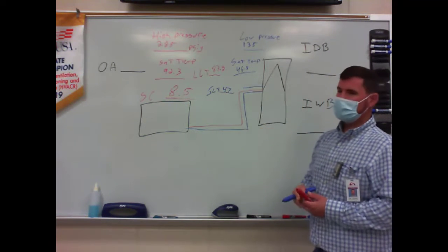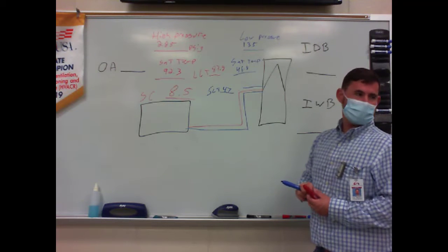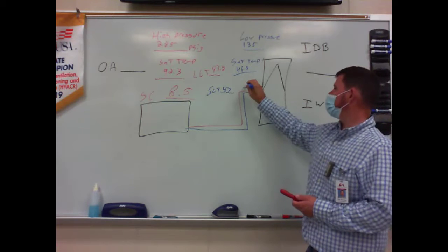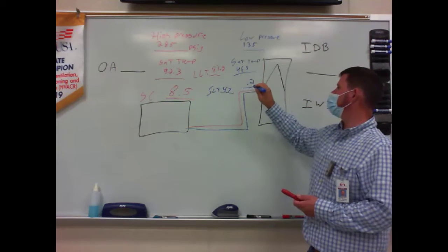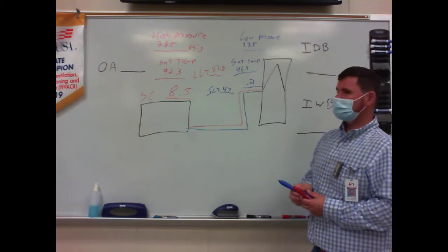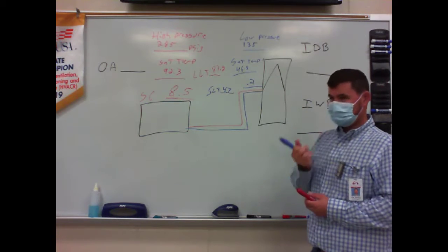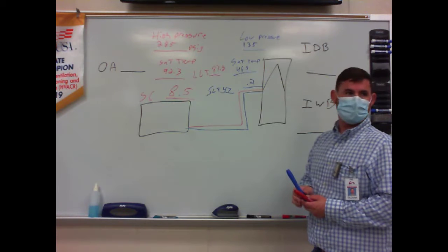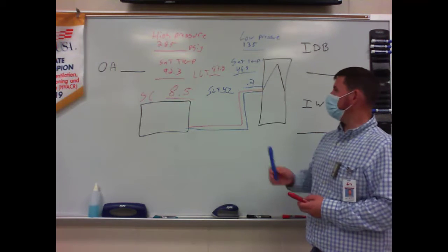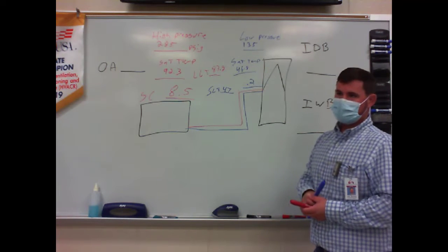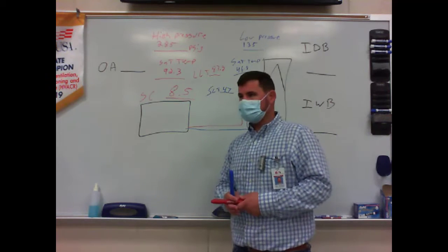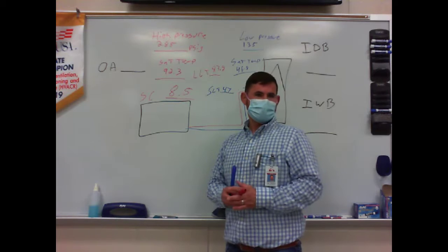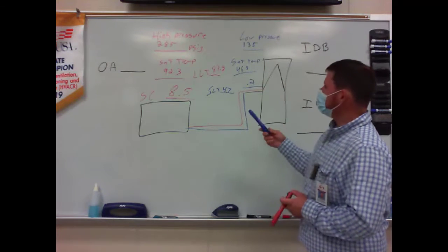So what was your superheat then? How much warmer was your suction line than your saturation temperature? That's right, which is almost nothing, right? Because our gauges probably aren't that accurate. So really we have 0 degrees superheat. Let's go ahead and fill in the rest of my information.